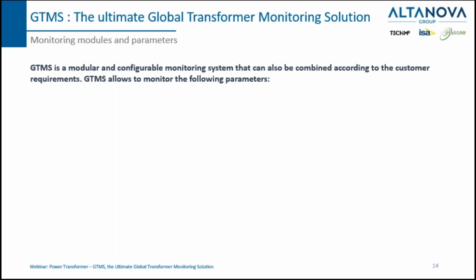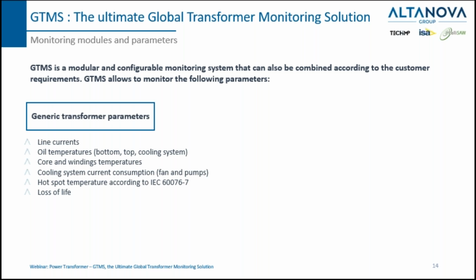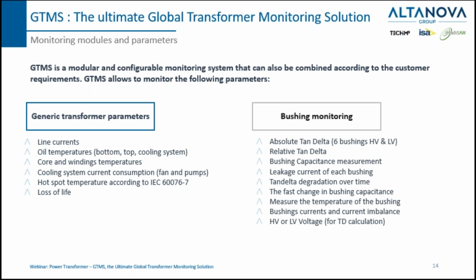In this slide, you can see the list of the parameters that can be monitored by the global transformer monitoring system. Basically, we have 4 modules. The first one we call generic transformer parameters. You can see that we can monitor line currents, oil temperature, core and winding temperature, cooling system, hotspot temperature and loss of life. But also bushing monitoring in terms of absolute and relative tan delta, the capacitance values, the leakage current, the degradation of tan delta, and other parameters. These modules can be combined based on the customer requirements.